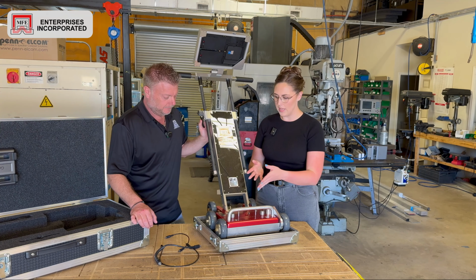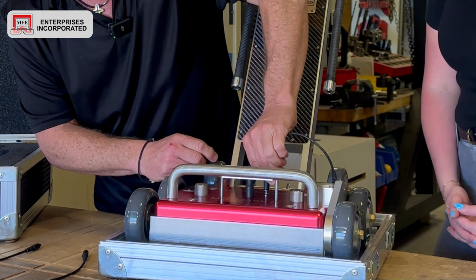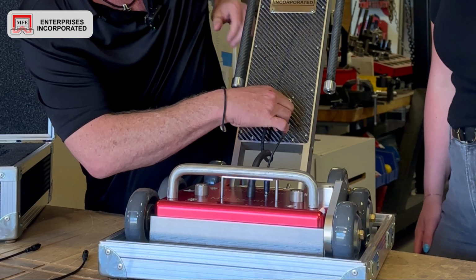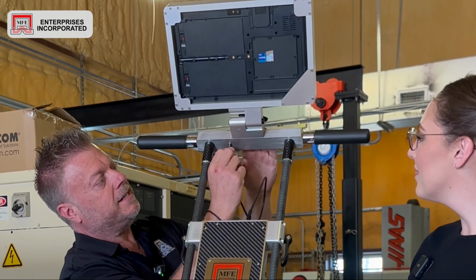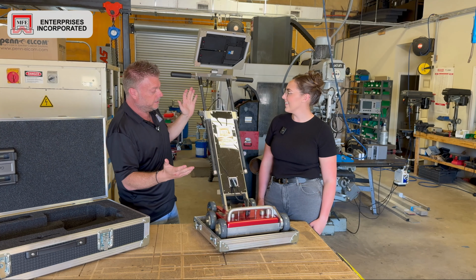And then the last step would be adding the cables on? Yep, I'm gonna add our 3 cables that come with the machine. These are advanced mil-spec connections, and they have a little O-ring on them. I'm gonna snap that down. That one went on real easy. It goes red dot here. That was our signal cable. This is our encoder cable. The encoder is nothing but a digital tape measure, and that gives us the ability to know precisely where the defects are distance-wise from where we started. This one is our electronics cable right here, and this is going to combine all that data after we've amplified it up to our Getac tablet up here. Amazing. And that's it. It is assembled, and what we do next is the function test.